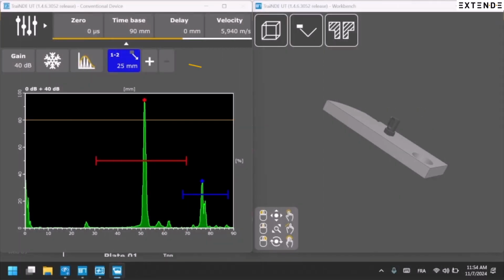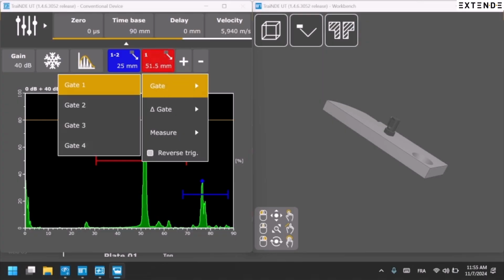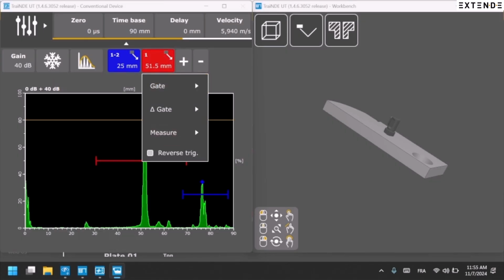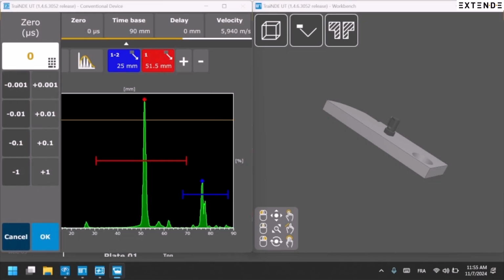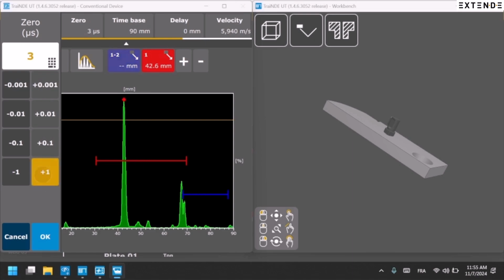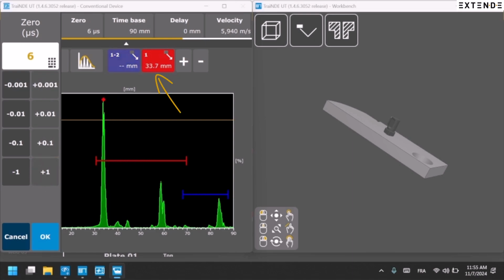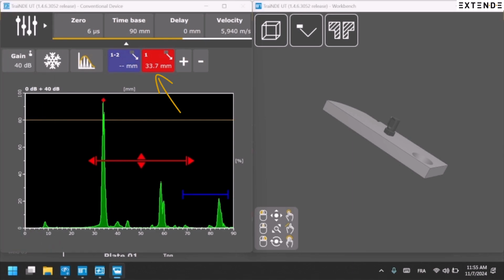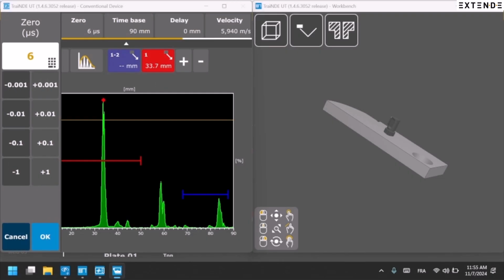Add a second gate's information by clicking on the plus button to display the sound path measured by Gate 1. We can verify that the gate's information is correctly displaying the sound path measured by Gate 1. Change the zero until the sound path of Gate 1 measures 25 mm. You may have to change the gate settings, specifically start and width, to keep tracking the echoes.